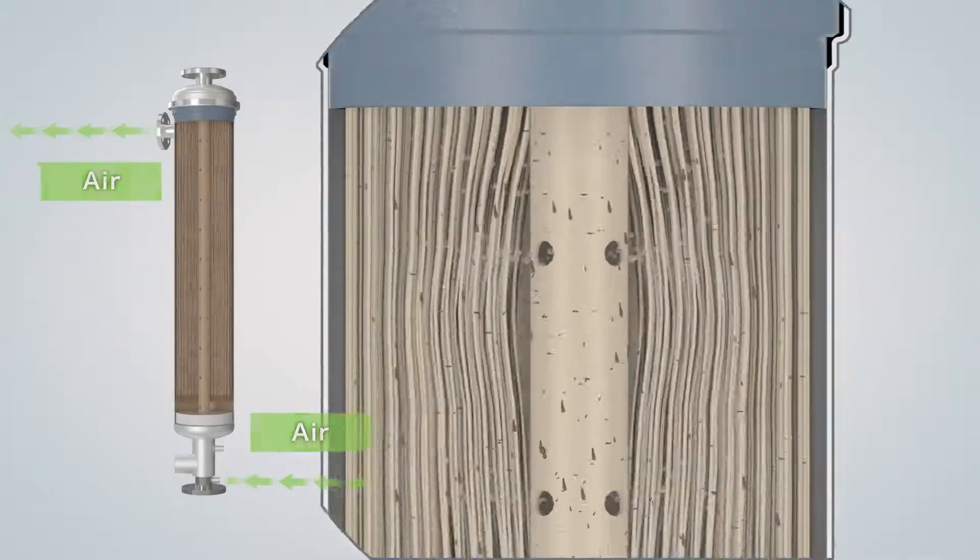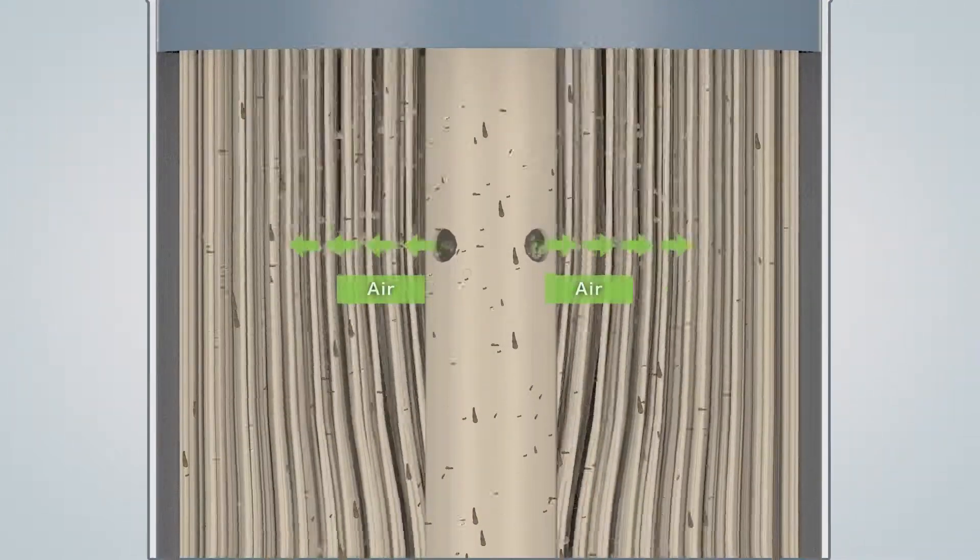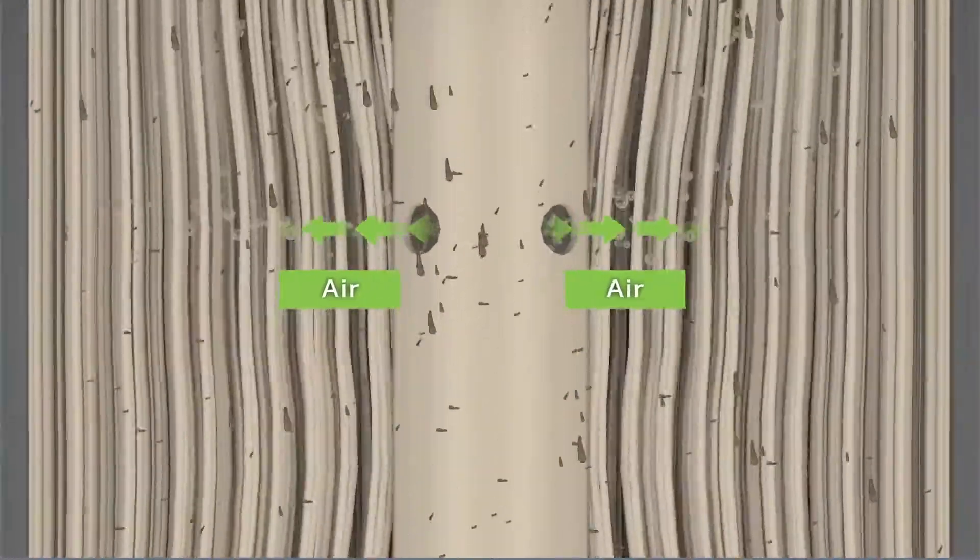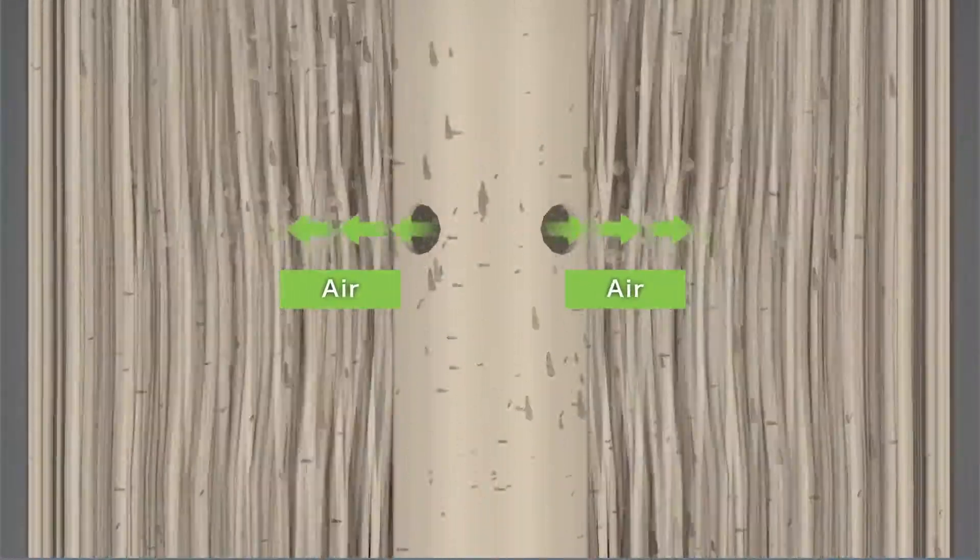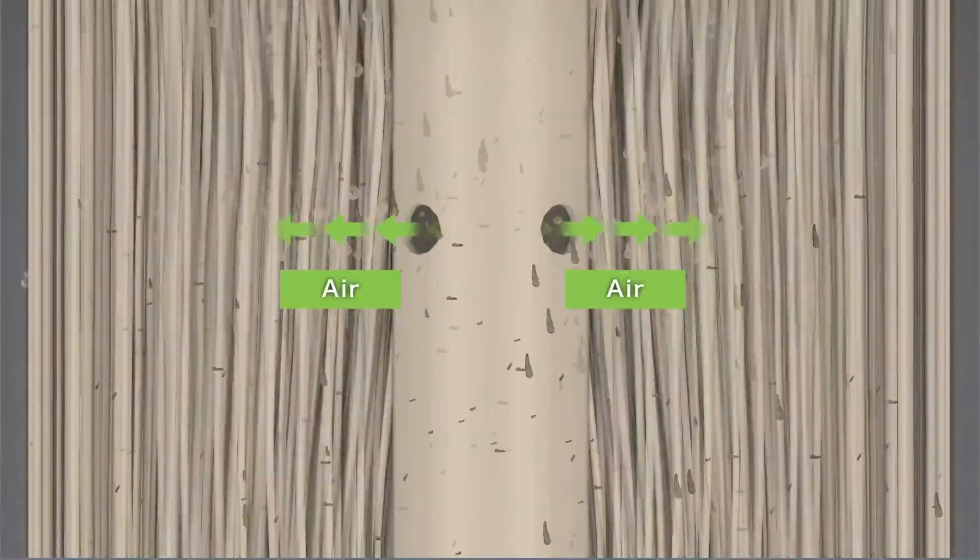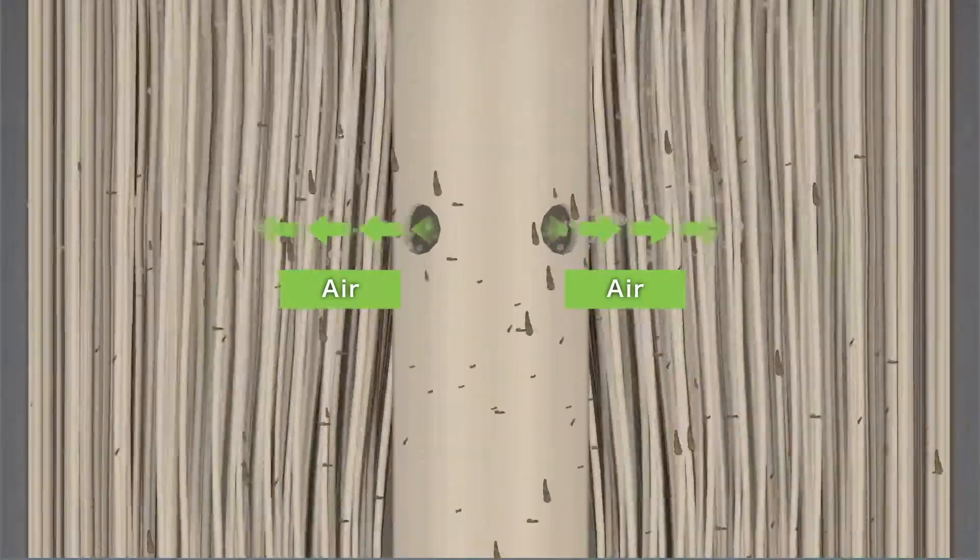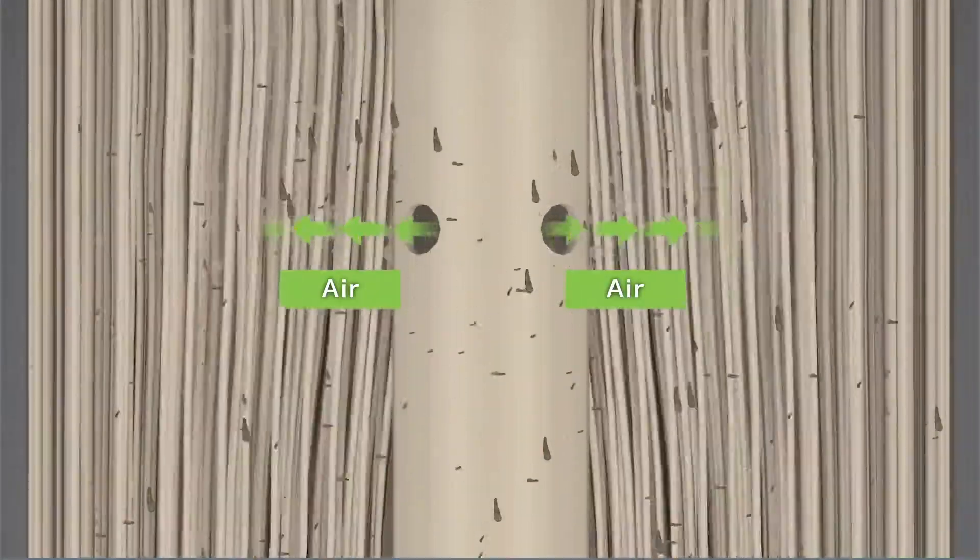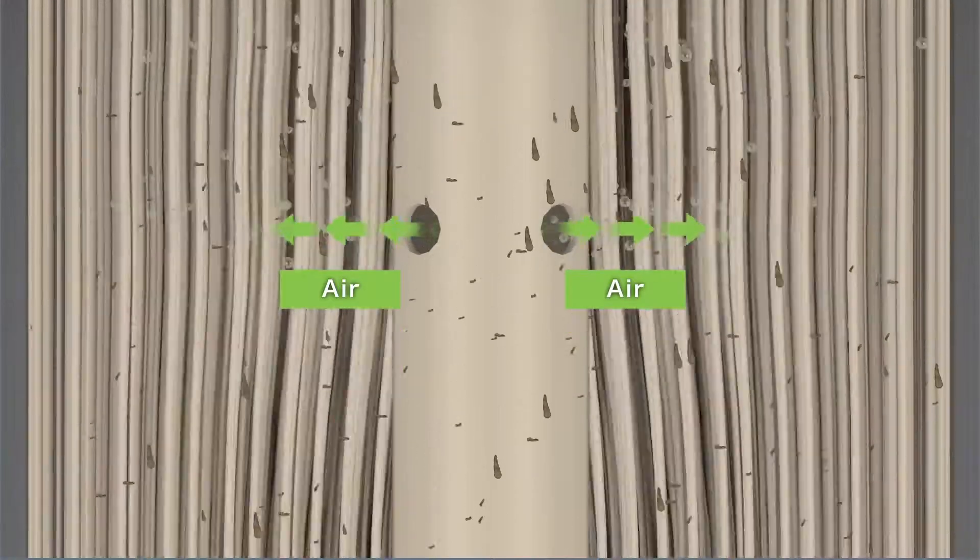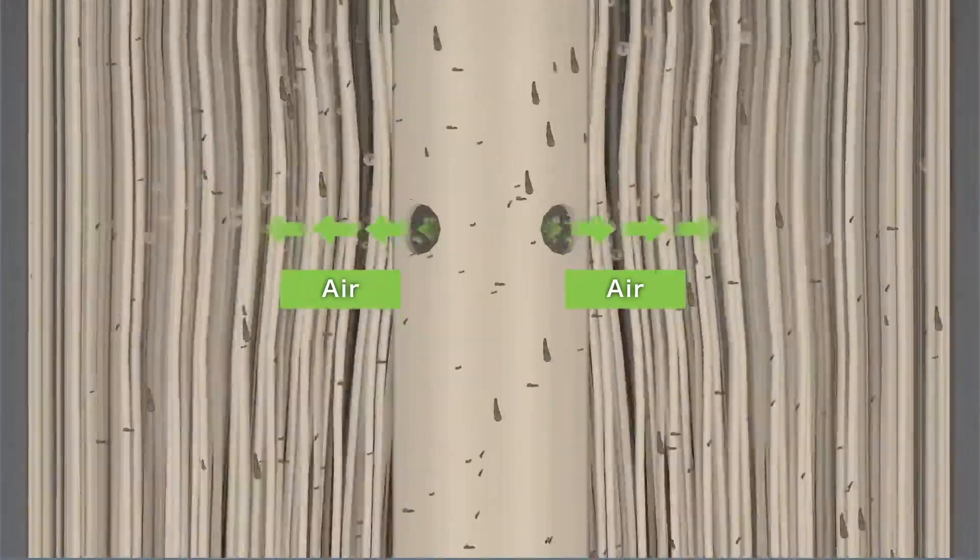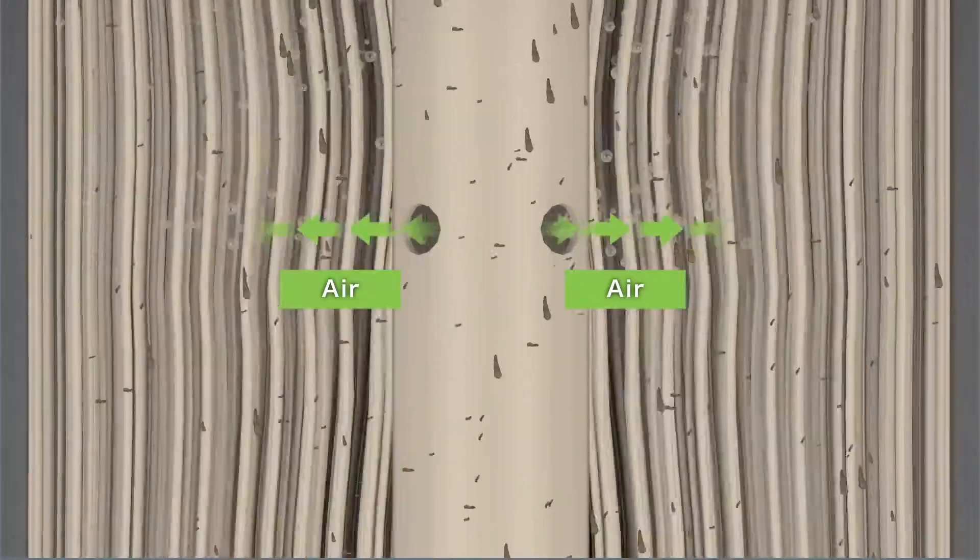By supplying air through the center distributor, bubbling cleaning of the upper part of the module, which could not be cleaned by the bubbling from the bottom part, becomes possible. In this way, by using two bubbling systems, the upper and lower, cleaning of the entire module becomes possible.